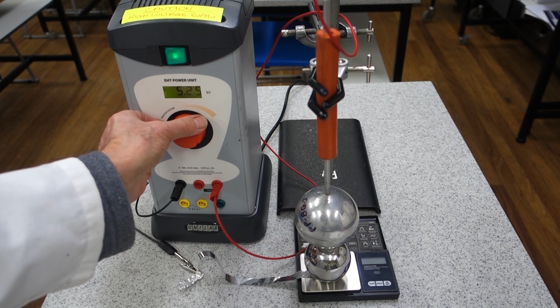So we're now taking some results, and you can see that on 0 volts, so before we've started, there's a reading of 0.02. We're now increasing the voltage up to 1 kilovolt, or 1,000 volts, and we've got a reading of 0.08 grams on the meter.